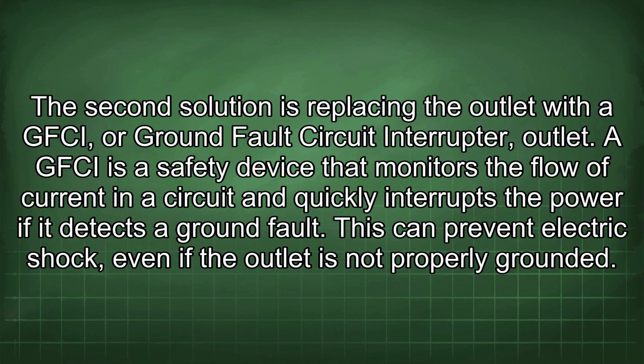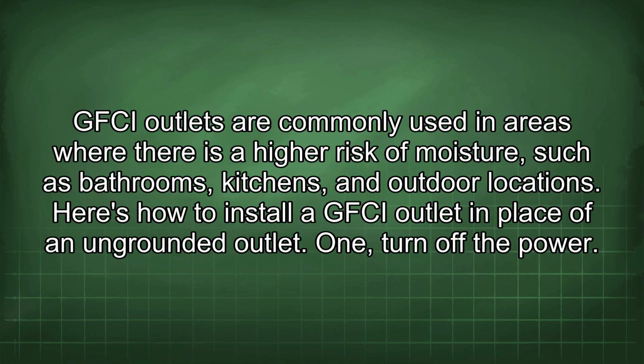A GFCI is a safety device that monitors the flow of current in a circuit and quickly interrupts the power if it detects a ground fault. This can prevent electric shock, even if the outlet is not properly grounded. GFCI outlets are commonly used in areas where there is a higher risk of moisture, such as bathrooms, kitchens, and outdoor locations. Here's how to install a GFCI outlet in place of an ungrounded outlet.